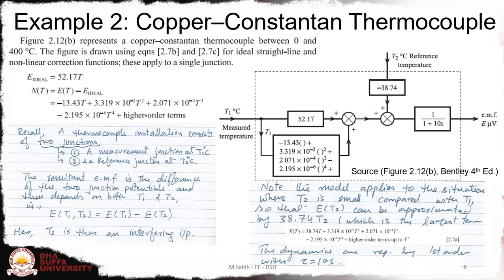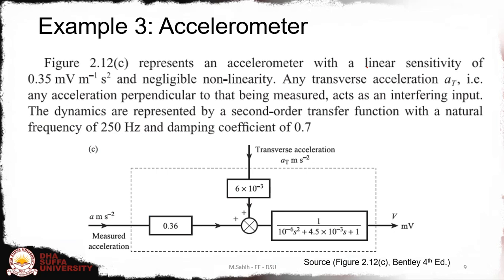Next is an example of an accelerometer, which represents the linear sensitivity of around 0.35 millivolts per meter per second squared. Nonlinearity is negligible, so it is not present. Here, any transverse acceleration—that is, any acceleration perpendicular to that being measured—acts as an interfering input, and the sensitivity constant is 6×10⁻³. The dynamics are represented by a second-order transfer function with the natural frequency of 250 Hz and a damping coefficient of 0.7, so ζ is 0.7.